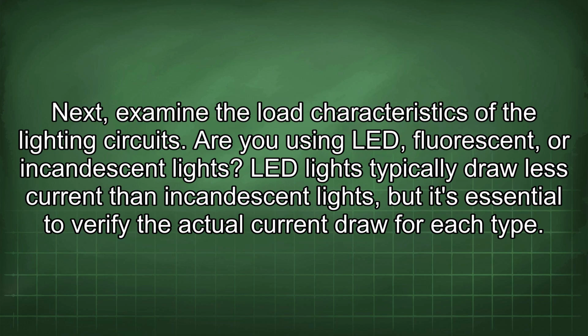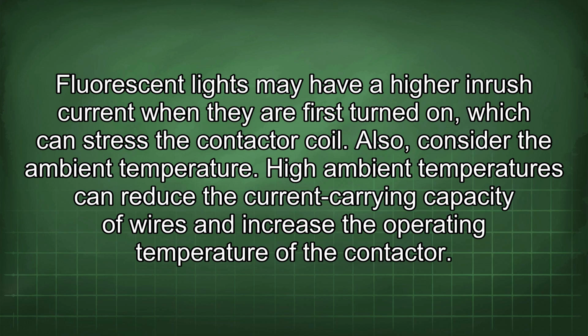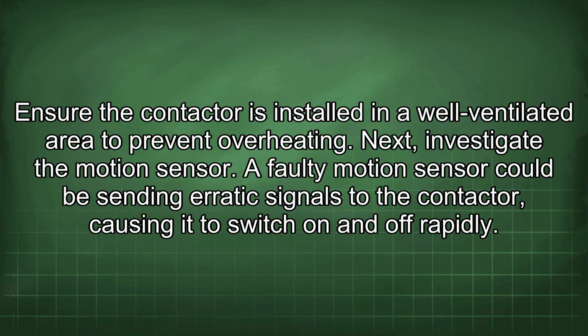Next, examine the load characteristics of the lighting circuits. Are you using LED, fluorescent, or incandescent lights? LED lights typically draw less current than incandescent lights, but it's essential to verify the actual current draw for each type. Fluorescent lights may have a higher inrush current when they are first turned on, which can stress the contactor coil. Also, consider the ambient temperature. High ambient temperatures can reduce the current carrying capacity of wires and increase the operating temperature of the contactor. Ensure the contactor is installed in a well-ventilated area to prevent overheating.